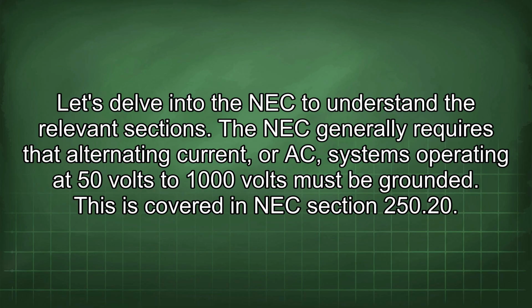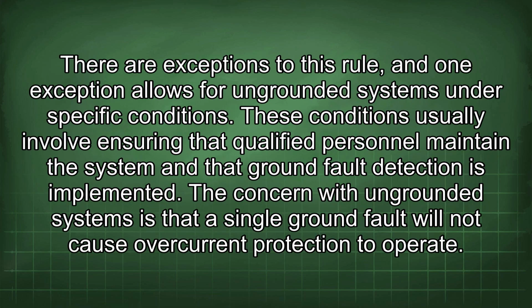The NEC generally requires that alternating current, or AC, systems operating at 50 volts to 1000 volts must be grounded. This is covered in NEC section 250.20. There are exceptions to this rule, and one exception allows for ungrounded systems under specific conditions. These conditions usually involve ensuring that qualified personnel maintain the system and that ground fault detection is implemented.